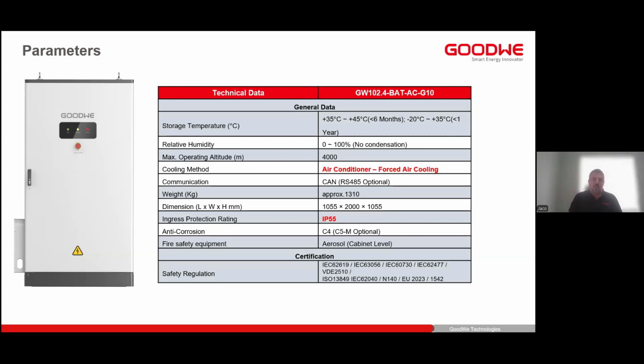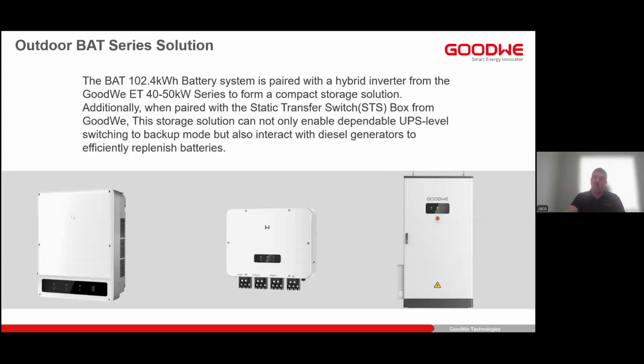The unit is IP55 rated, so fully outdoor compliant. And that completes the full outdoor solution. So it's the inverter, the STS, and then the outdoor battery. The inverter will be installed on the side as mentioned, but keeping in mind that the ET50 is also fully IP65 rated. We generally would recommend that there should be some kind of shading or something on top of the battery unit, just to avoid the air conditioning unit running all the time.